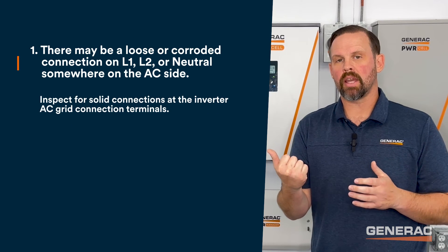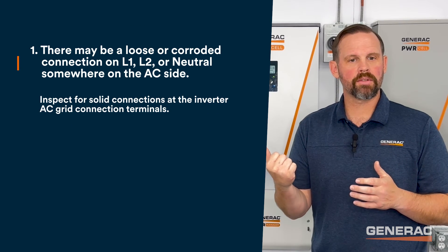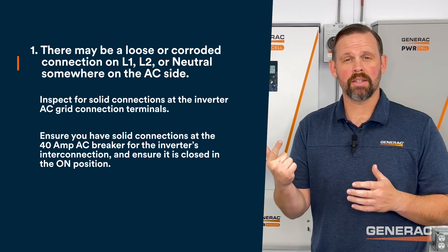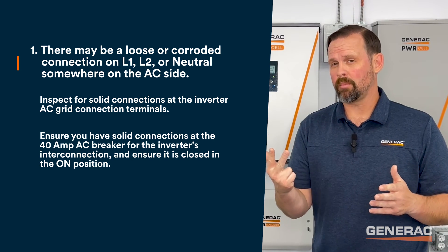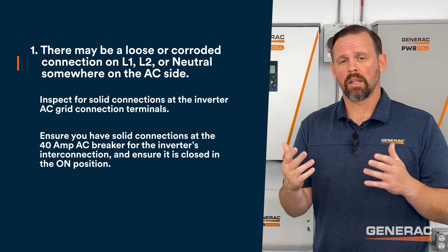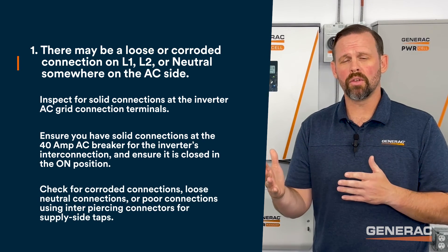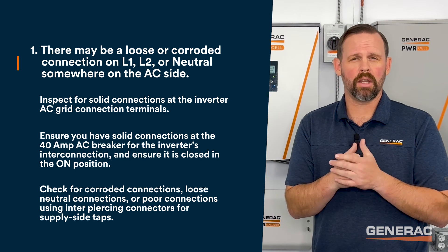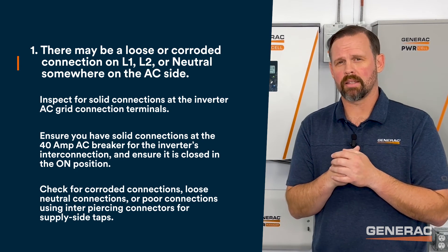Inspect for solid connections at the inverter AC grid connection terminals, ensure you have a solid connection at the 40-amp AC breaker for the inverter's interconnection, and ensure that breaker is in the on position. Likewise, check for corroded connections, loose neutral connections, or a poor connection with an inner piercing connector for a supply side tap.